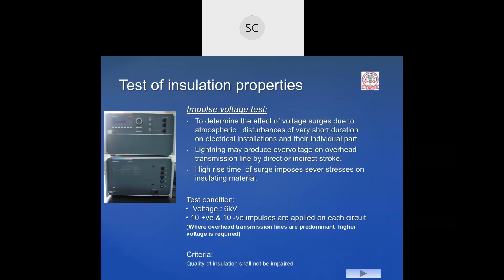Then next is the high voltage test. It is a simple high voltage test to check the insulation properties, to ensure that the meter is properly insulated, proper clearance is given, and the creepage distance is properly maintained. There are two protective classes available.